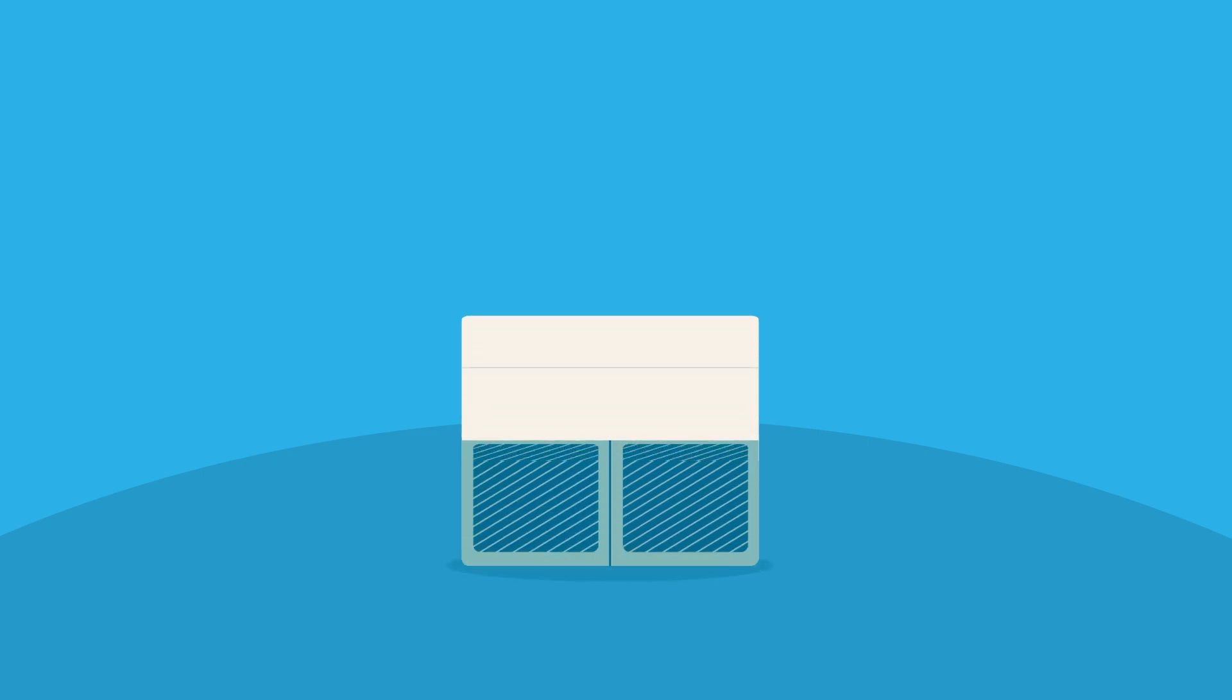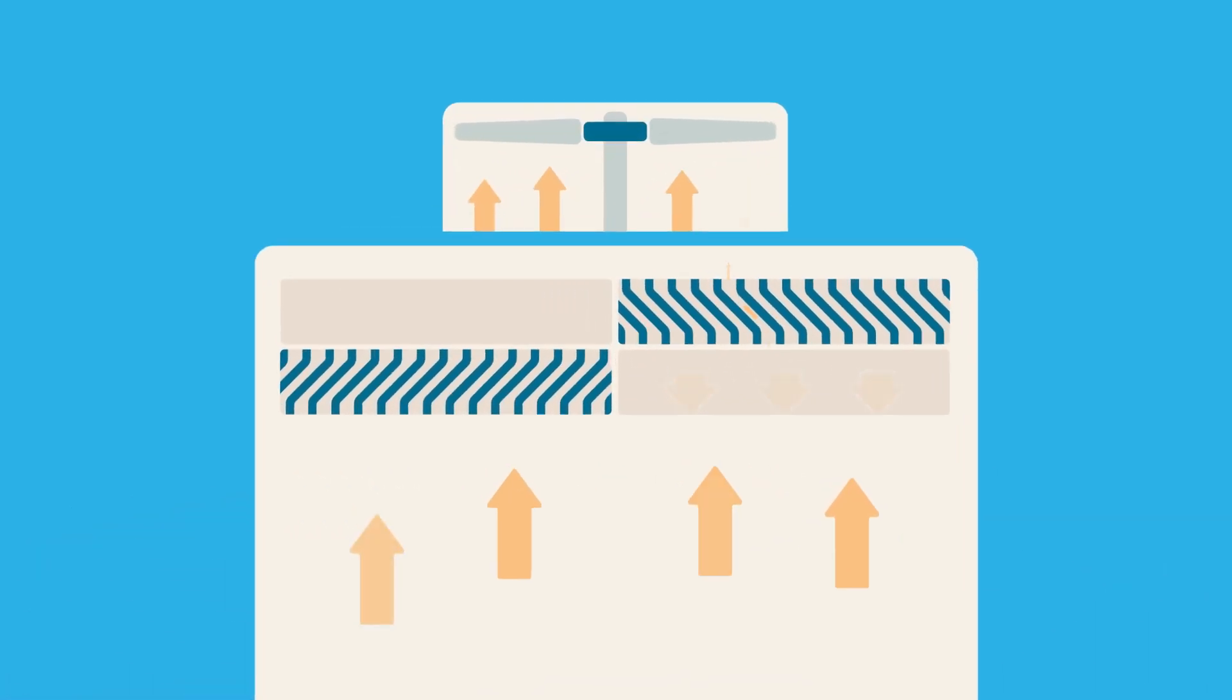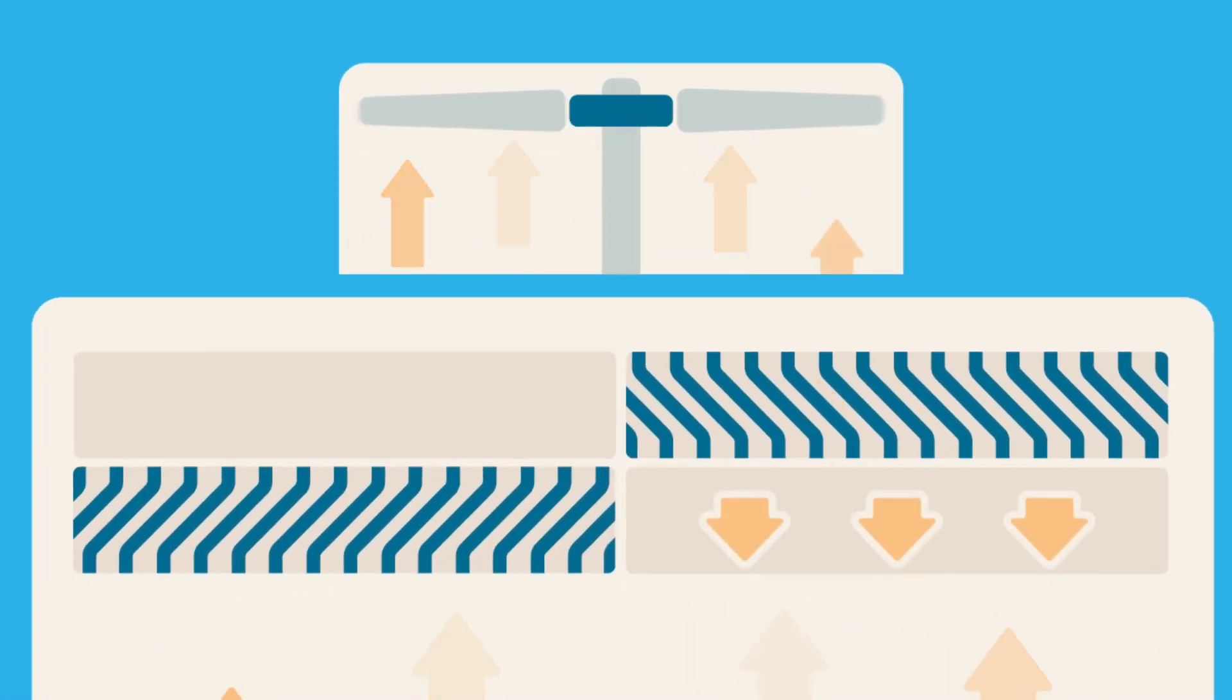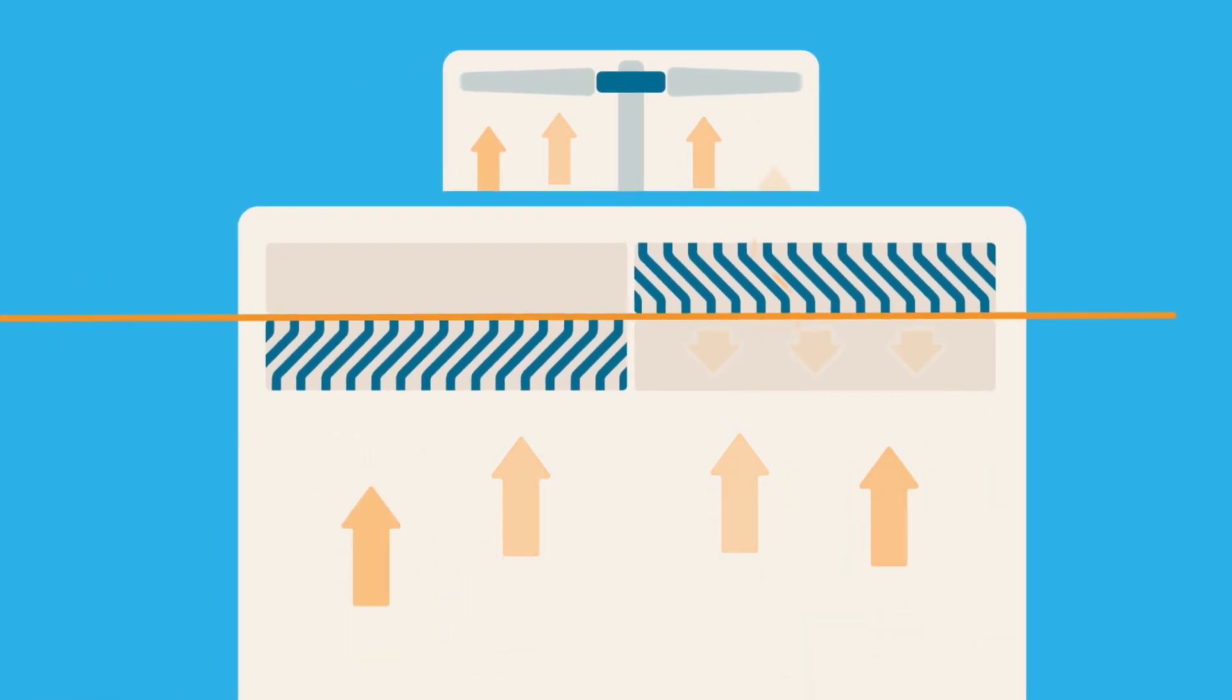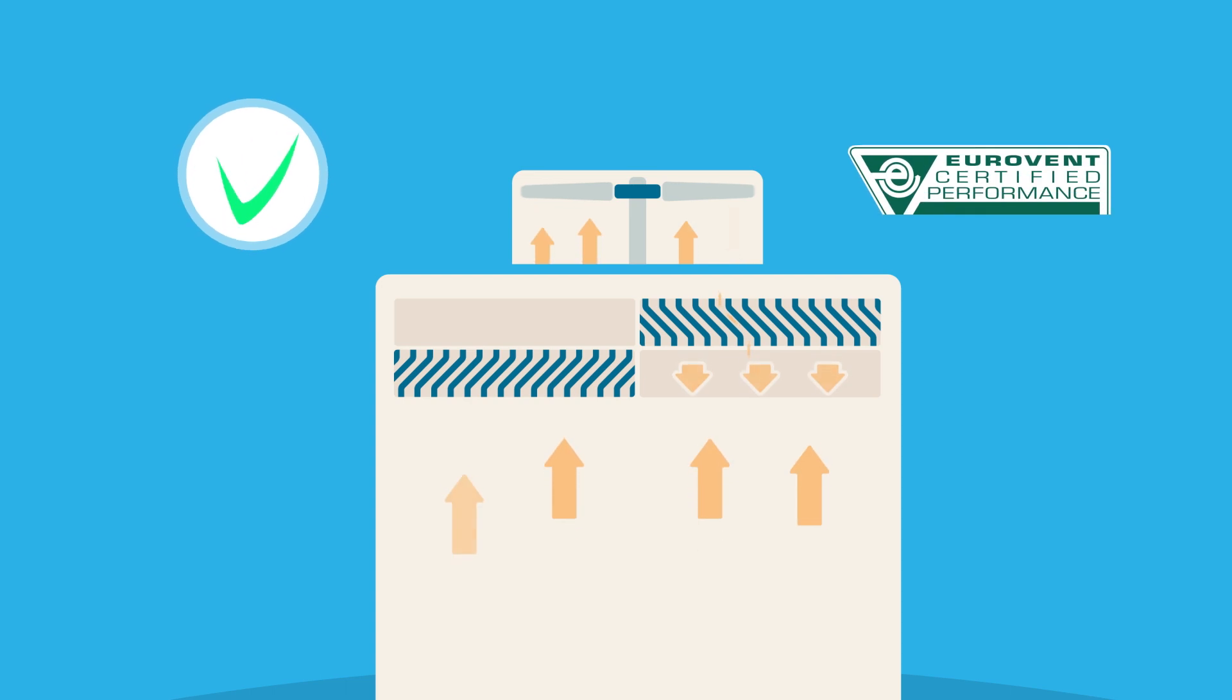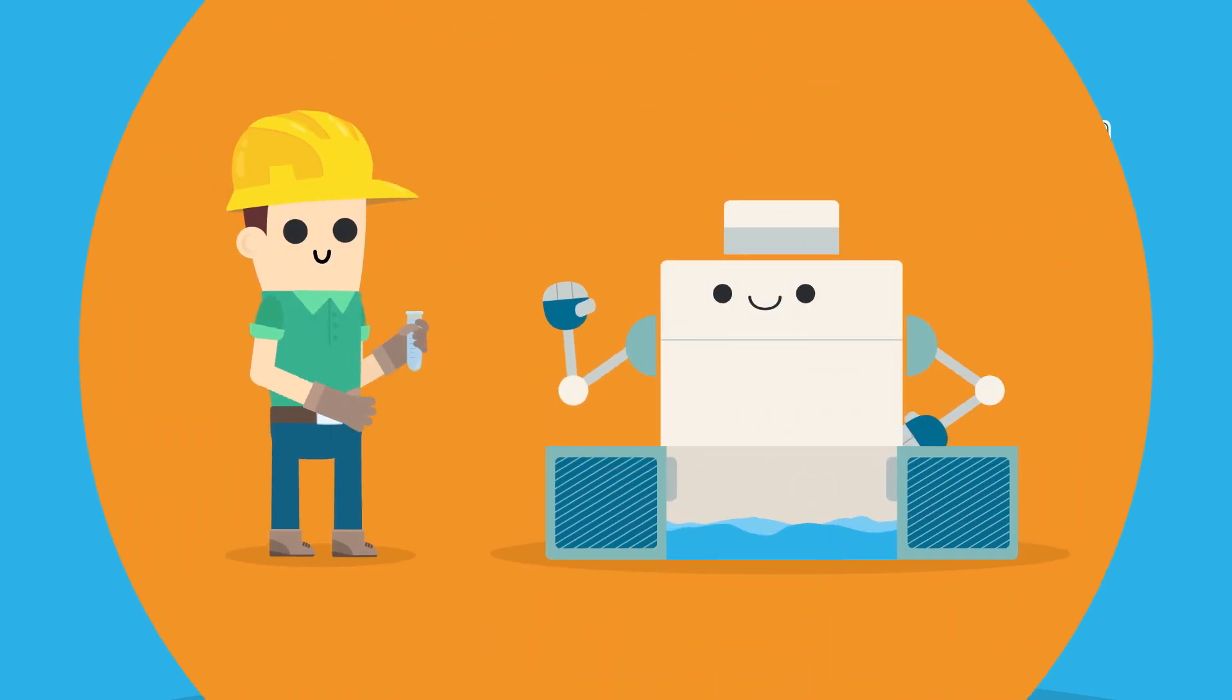In particular, it is important to check that the droplet separators are clean and in good condition, that they adhere properly to one another, create a uniform block and are suitably directed in accordance with the manufacturer's instructions.